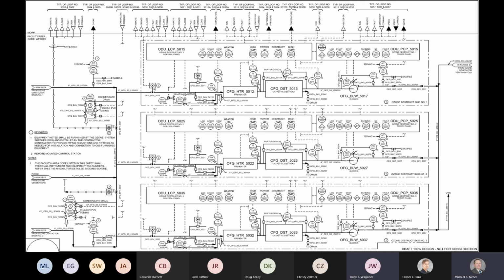The inline instrumentation, like some inline flow meters, are also procured by electrical. If it's in line with the process mechanical piping, the process mechanical folks will install that instrumentation provided by electrical. If it's a plug-in off of a weldlet, process mechanical provides the connection and electrical installs the instrumentation.